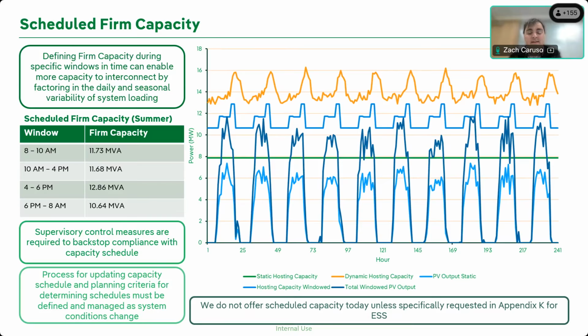One thing I'll point out is that depending on how you slice those buckets, you still end up with a worst case scenario. If I'm doing a summer and I say summer is from May through September, I'm getting both the very hot days where I might have a significant amount of capacity, and also, particularly in upstate New York, those cooler 60- or 50-degree days that sprinkle themselves into May or September, where we would see a lower minimum load. So the benefit is that we are able to utilize more capacity, but we perhaps don't get all the way up to that orange line in this diagram.